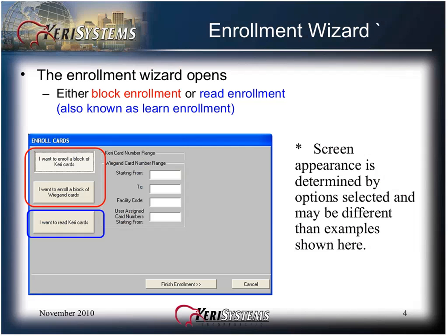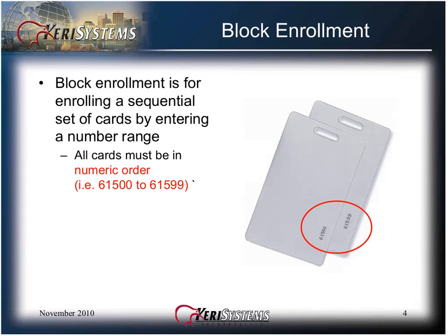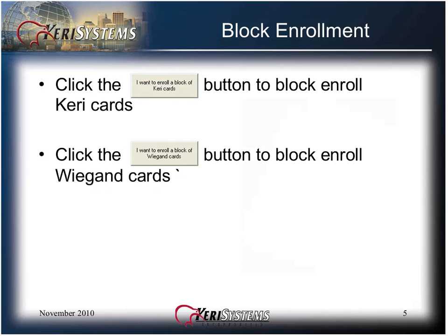The screen appearance is determined by options selected and may be different than the examples shown here. Block Enrollment is for enrolling a sequential set of cards by entering a number range. All the cards must be in numeric order. You must know the facility code of the credentials for proper block enrollment. Begin the Block Enrollment by clicking the I Want to Enroll a Block of Carry Cards button to block enroll Keri cards, or click the button to block enroll Wiegand cards.